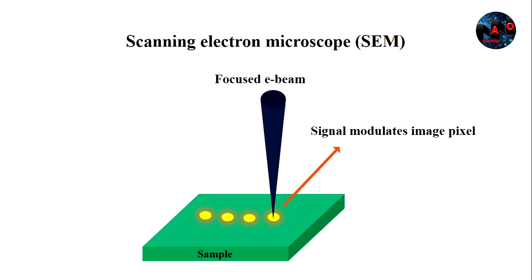In SEM, the electron beam is focused to a spot and is scanned sequentially across the specimen. At each location, signals are emitted from the specimen and collected by detectors. The detector signal is synchronized with the known location of the beam and the specimen.